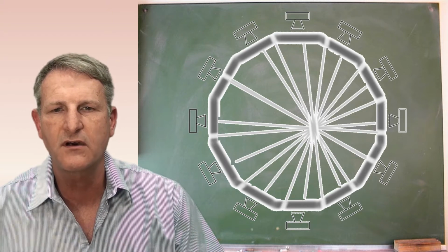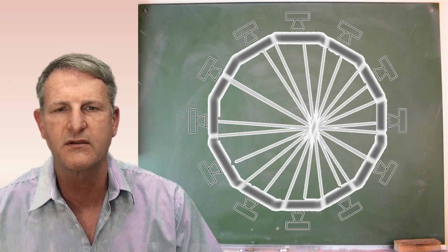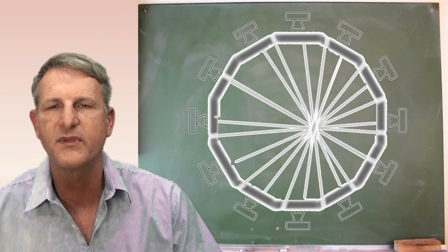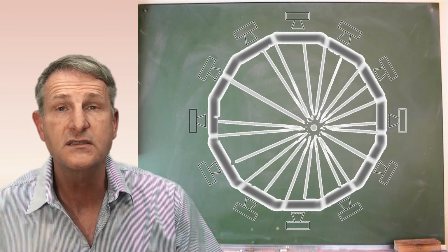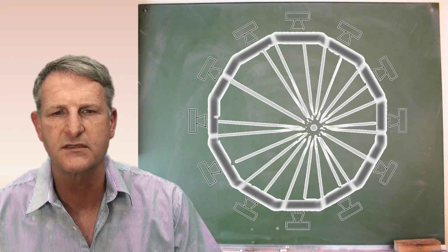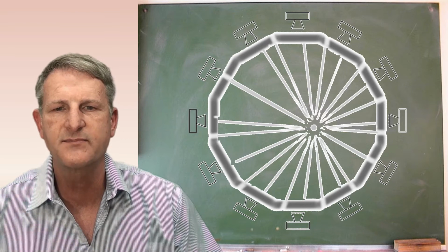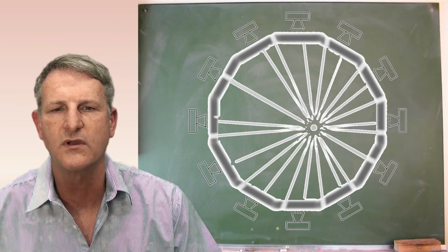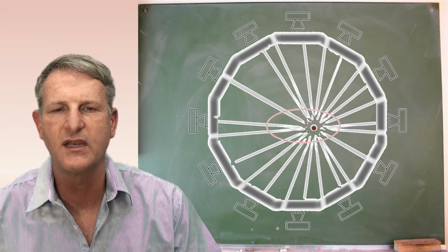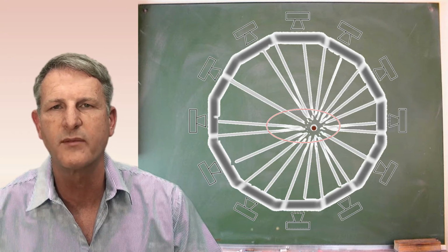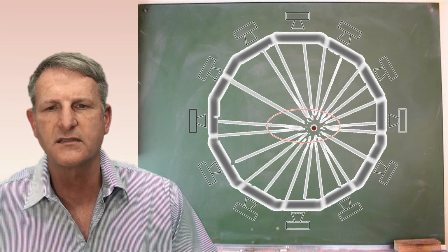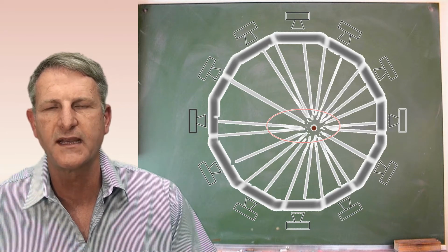To get rid of the star artifact, one can of course erase the information on either side of the back projected line and repeat for each projection. This technique is called filtered back projection. The mathematics is best performed in the frequency domain using fast Fourier transforms, but this is a topic for another talk. Just indicate in the comments below if you would like to learn more about this topic. When done correctly, the final result is a good representation of reality.